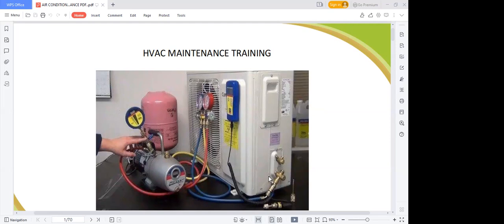So what I'm saying is the problem we have in Nigeria is irregular power supply. Even if they bring the light, the voltage is not sufficient to power up most of our equipment. In order to protect your equipment, you need something to check the quality of power coming into it, because the essence of the AVR or AVS is to regulate. If the power is sufficient, it allows it to go through your equipment and power it on. If it is not good, it shuts the system off. It will not power on, thereby saving the life of your equipment. Because if such power gets to your system, your compressor can be damaged and your electrical panel can be burnt. And if, God help you, you don't have the part in the market, that equipment becomes useless to you. So it regulates and protects your equipment.